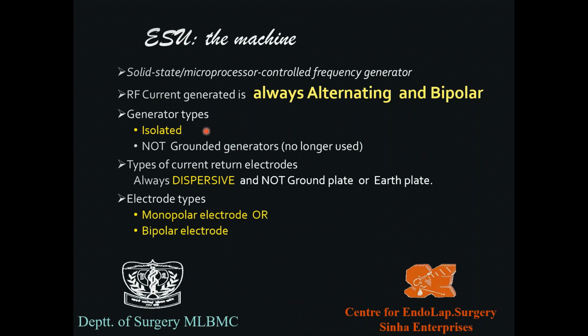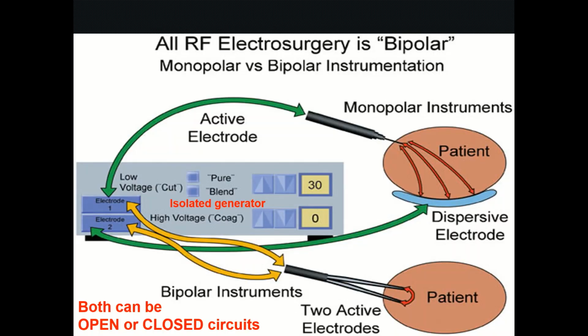Remember that plate which you put underneath the patient, that's very, very important. That is what is bringing the current back to the machine. Initially that used to bring the current into the earth. That way initially the term was earth plate, but that is no longer used. And the electrode types can either be monopolar or bipolar. We all know that. Now to explain these, let's see what bipolar means.